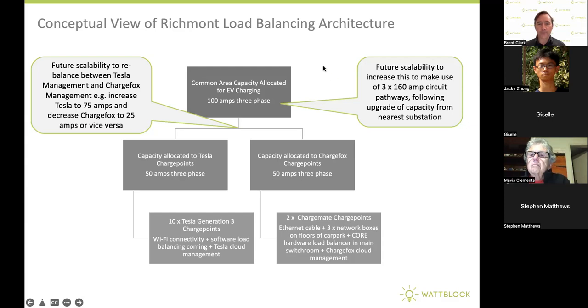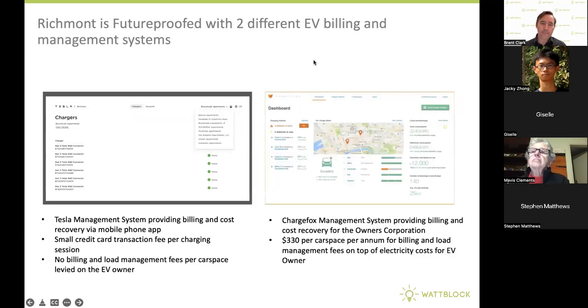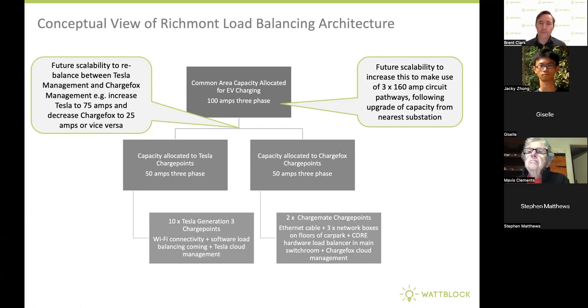They're also extensible in that they've got 160 amp circuit pathways to the 3 distribution boards on each floor of the basement car park. So if at a future point in time they increase the capacity from the street into the building, say by another 100 amps, they could turn this to 200, and then go 100, 100, or 150 or so, without having to install thicker cables from the main switch room down to the distribution boards on each of the 3 floors of the basement car park.